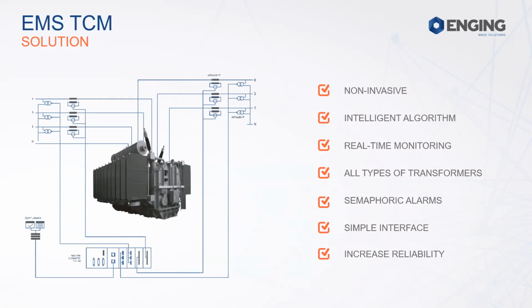...monitor of the transformer. The second reading will read after the first reading and will also make the comparison to the original characteristic plate. This goes on and on, every 3 seconds. That's why we call it a smart or intelligent algorithm: it gives you the actual status of the transformer in real time, and it is completely adaptable to all kinds and types of transformers.